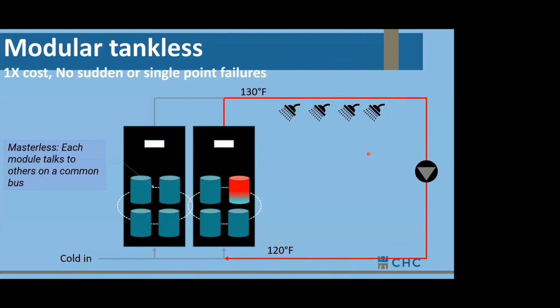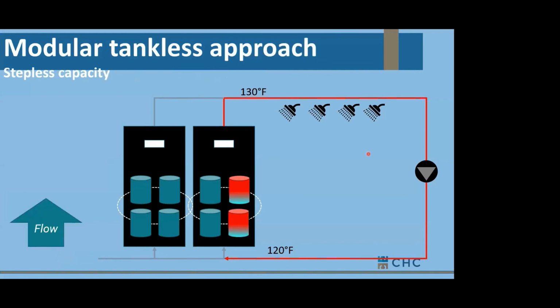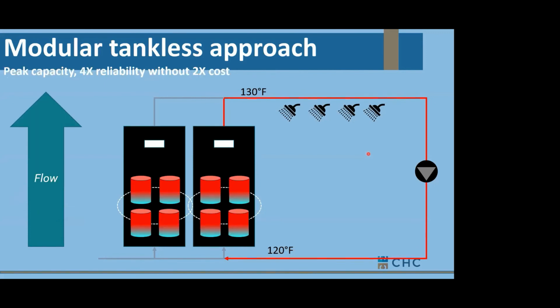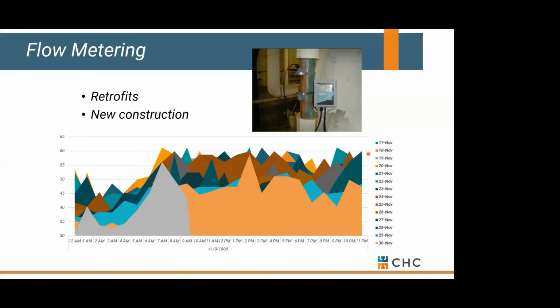Now, when we're just recirculating the building, we're going to have a very small load. But as the loads increase, you're going to bring on more engines to recover that. If the load continues to increase, you can start rotating or cycling which engines are going to fire based on how aggressively they fired last time. So they call it masterless control, but basically they're trying to average runtime and aggressive behavior. So they do track that. And if you get to a full load condition, all engines are going to fire. Okay, it's really that simple. And then they stage on and off as the loads fluctuate in our domestic system.